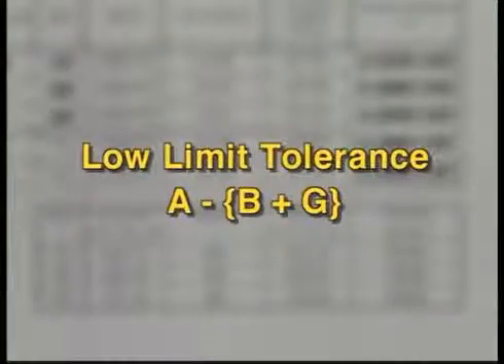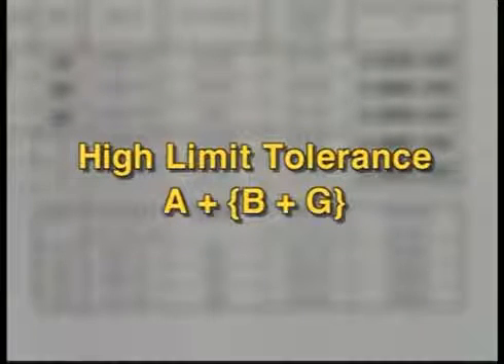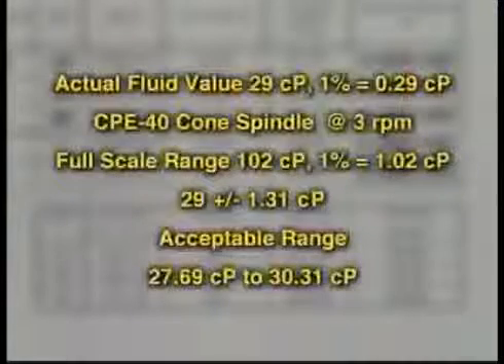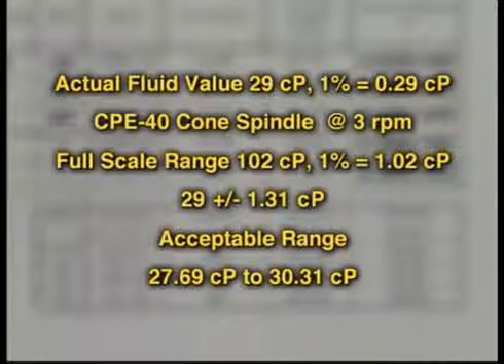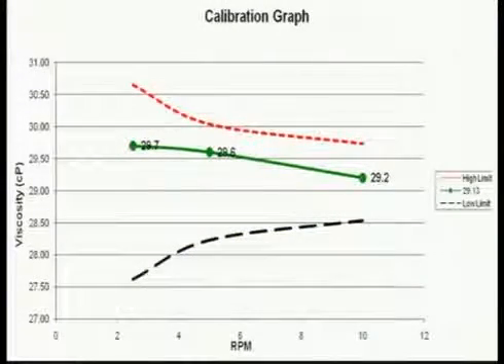The low limit tolerance is column A, the actual fluid value, minus column B plus G, 1% of the actual fluid value plus 1% of the full-scale range being used. This high limit tolerance is merely column A plus column B plus G. Simply put, if the actual fluid value is 29 centipoise, then 1% of this value is 0.29 centipoise. At a speed of 3 rpm, the full-scale range is 102 centipoise, and 1% of this value is 1.02 centipoise. Thus, the tolerance on the fluid at this speed with the CPE-40 cone spindle would be 29 plus or minus 1.31 centipoise.